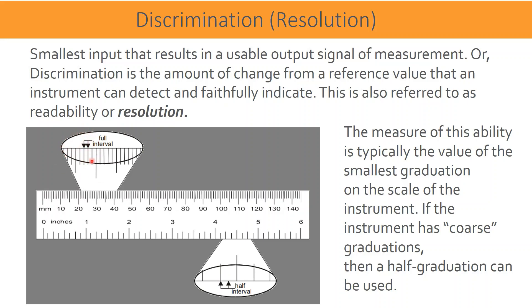As stated for the pressure gauge, the minimum value indicated — that smallest graduation value — is called the resolution. If the instrument has coarser graduations, then half of the graduation value can be taken for calculations in the measurement uncertainty.